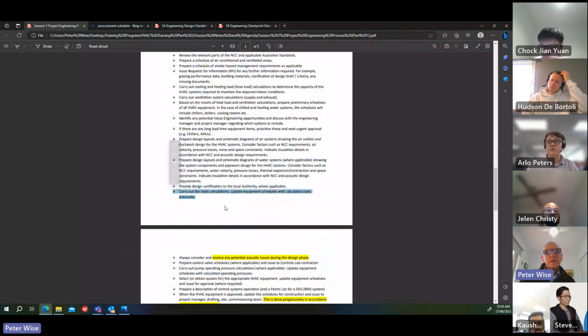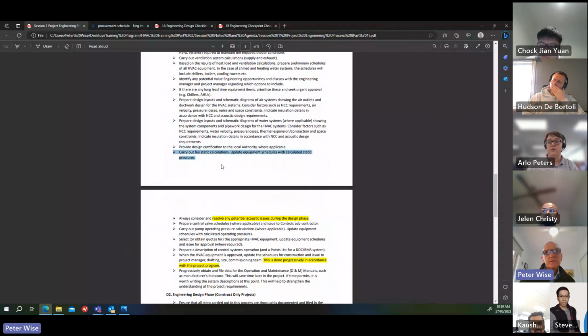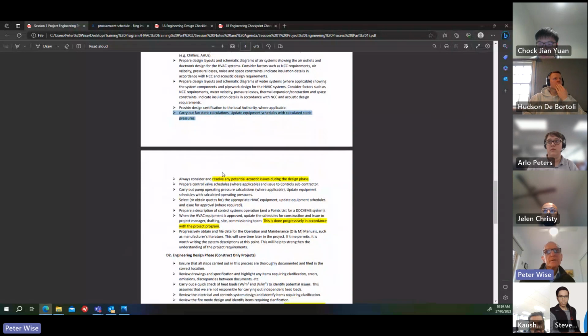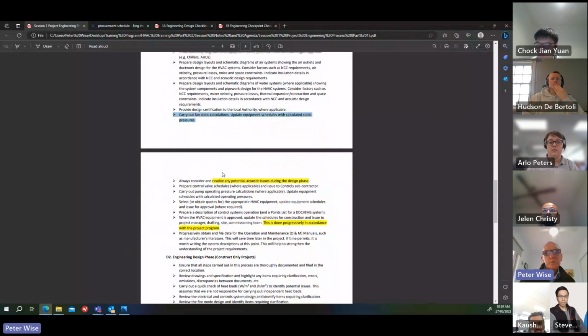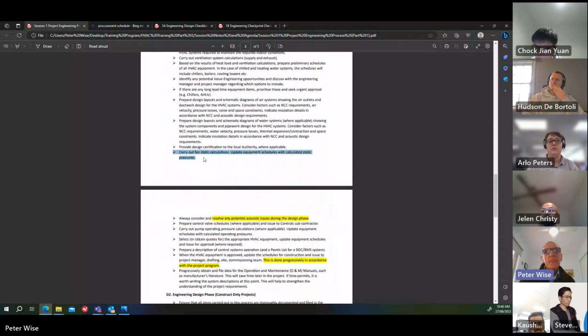You can carry out fan static calculations, and then update the equipment schedules with the calculated static pressures so that you're ready to get firm pricing on that equipment. Once you've completed your static calcs, you know the flow rates and what sort of fan you need, and you can get the schedule updated with the correct data.